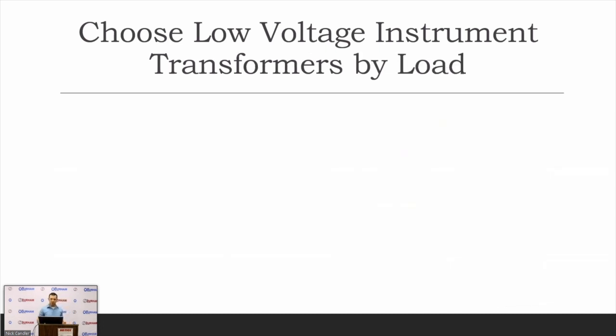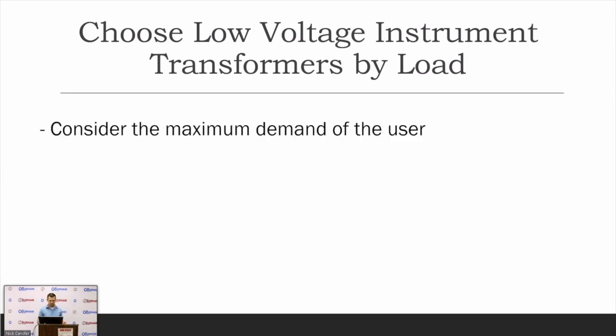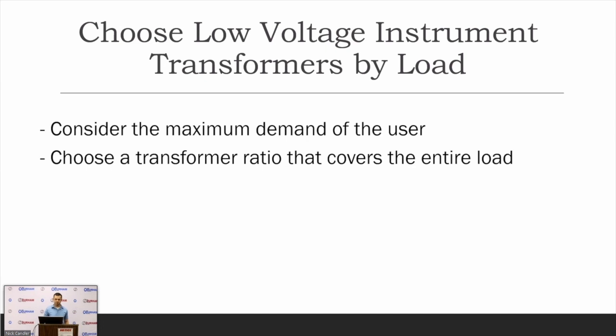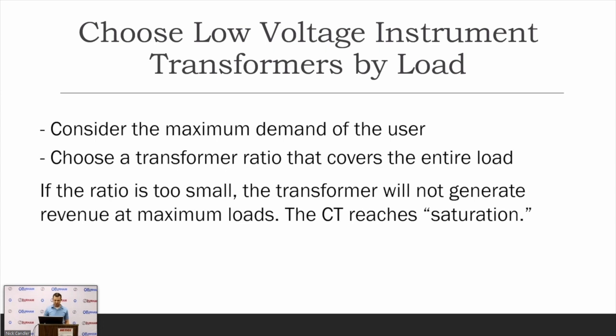We want to talk about the load as well. The customer's usage is a huge factor. We want to consider the maximum demand of the user. We want to choose a transformer ratio that covers the entire load, and that includes the rating factor. So we want to make sure that we size by the rating factor and not necessarily the nameplate. Historically, a lot of folks thought, well, we've got an 800 amp service. We need an 800 amp or an 800 to 5 transformer. Well, that's not actually the best way to go about it.